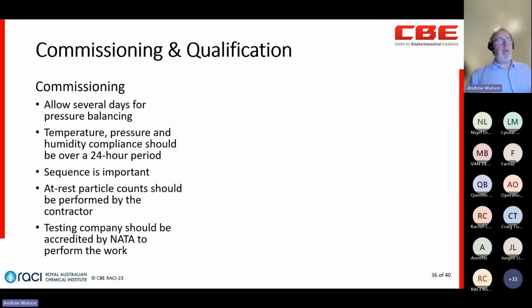Commissioning and qualification, just a couple of key things to note. Number one, when you're commissioning a facility and you've specified what your temperatures, humidities and pressures are, it's not just watching a gauge, seeing the number and saying, yep, tick, got it. You've got to allow a certain period of time, like a 24-hour period or even a 7-day period, to demonstrate that the facility is able to maintain those over that duration. It's the thing that holds up the finishing of commissioning a facility. Number one, trying to get the pressures to balance, but number two, actually trying to demonstrate that the facility is stable.